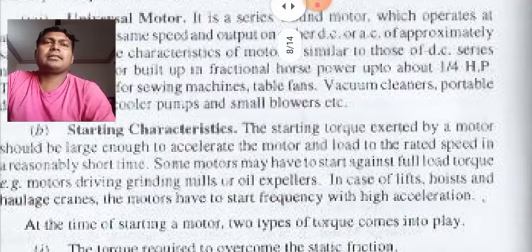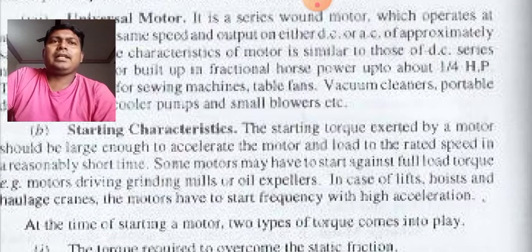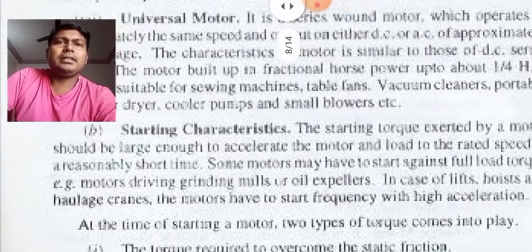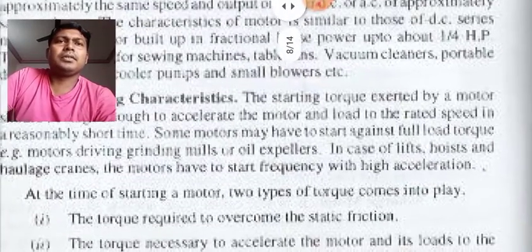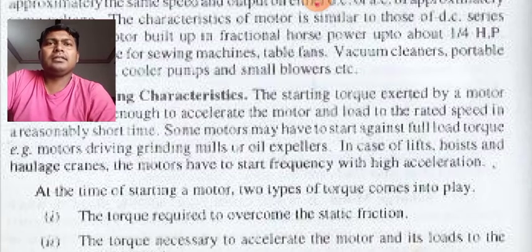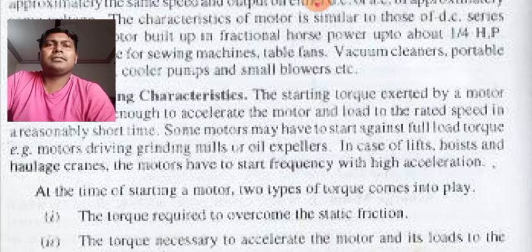Now the starting characteristics. The starting torque exerted by a motor should be large enough to accelerate the motor and load to the rated speed in a reasonably short time. Some motors may have to start against full load torque, for example, motors driving grinding mills or oil expellers. In the case of lifts, hoists and haulage cranes, the motor has to start frequently with high acceleration.